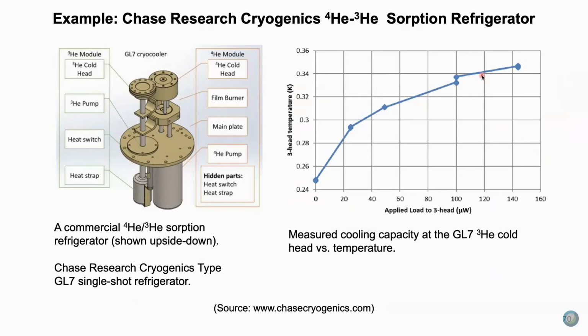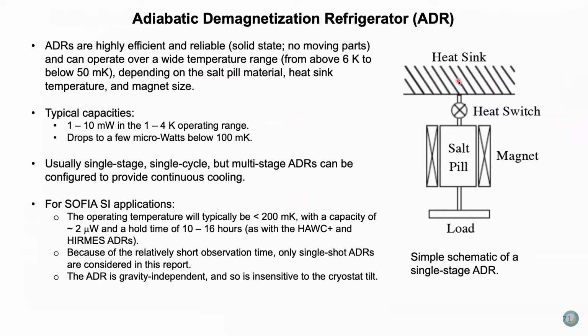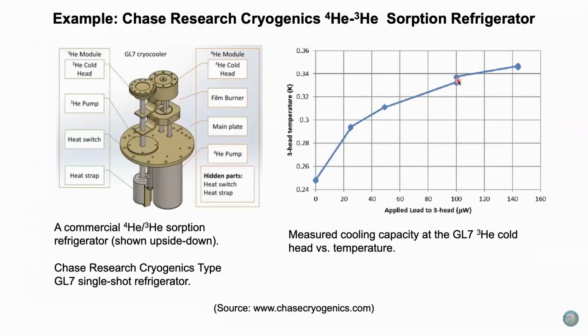And here is one of these tandem helium-4, helium-3 sorption refrigerators. Again, it's a Chase Research unit. And on the right is the load curve for the helium-3 head. Quite a bit, 100 microwatts at 0.34 Kelvin. That's quite a bit of heat cooling capacity. So that's it for the sorption refrigerators. Any questions on that section?